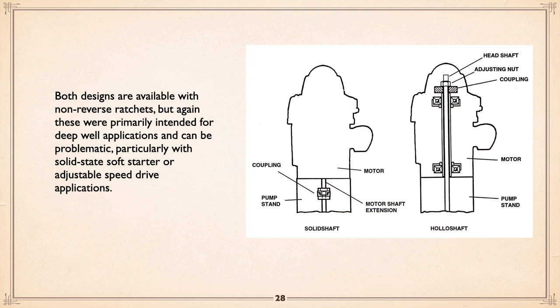And you see the hollow shaft motor, how the shaft itself has bearings top and bottom, but it's actually hollow. So there's an extended shaft, the head shaft as they call it, that extends from the pump shaft up to the very top, where there's an adjusting nut allowing you to ultimately adjust the impellers down below or compensate for shaft stretch and all that. And then there's a driven coupling piece. We'll get into that a little further on too.